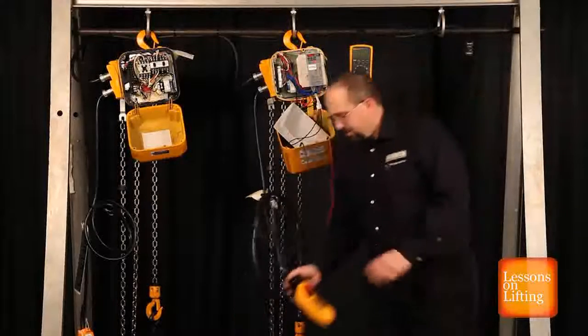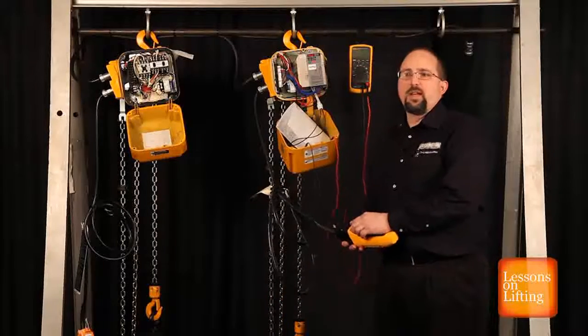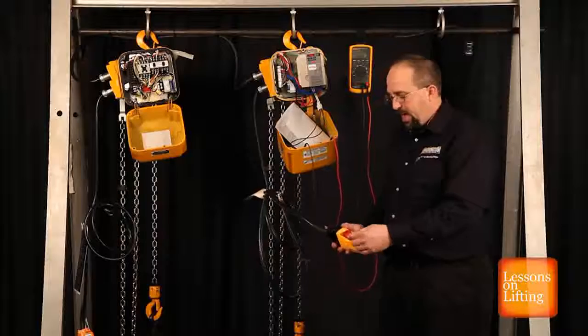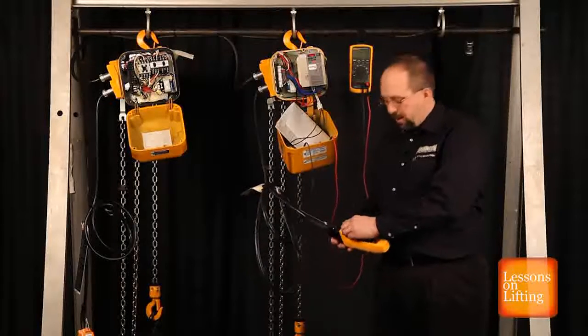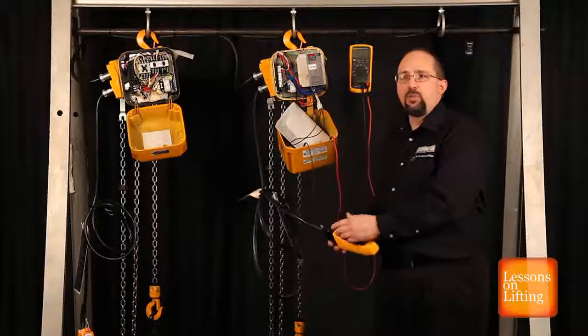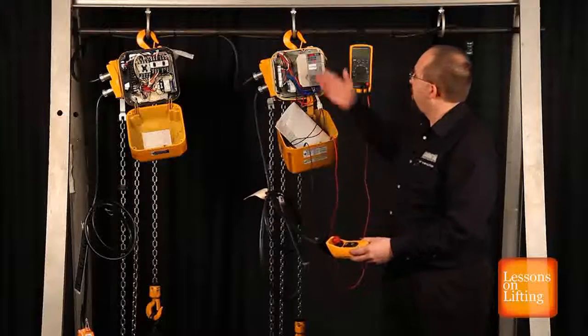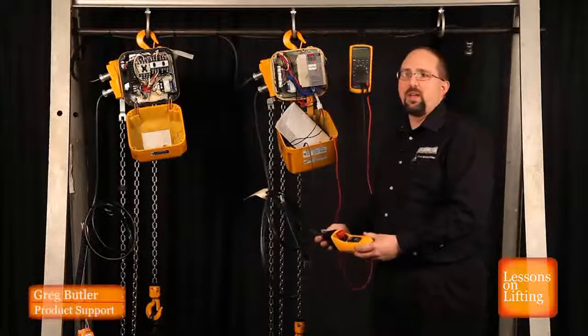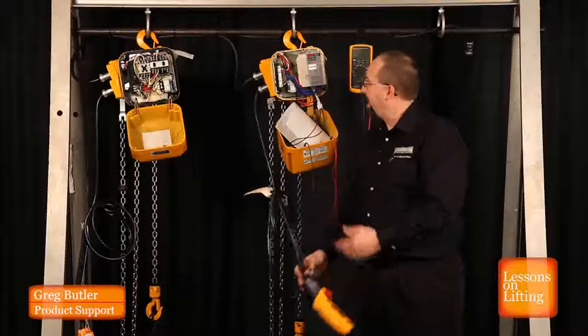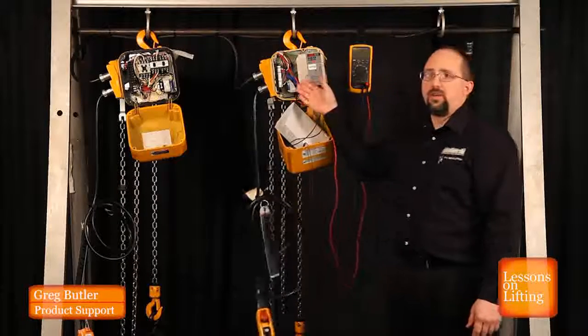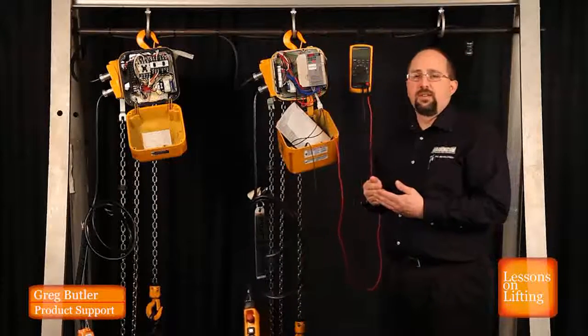We'll start by making sure the e-stop button is released, and to do that, you just rotate it counterclockwise or clockwise, and it should pop out. The e-stop button's released. We still have the HBB, which means that we're not getting that signal to the interface board that the e-stop is released.